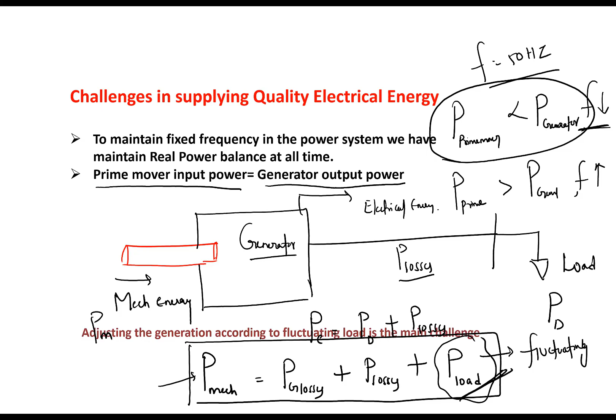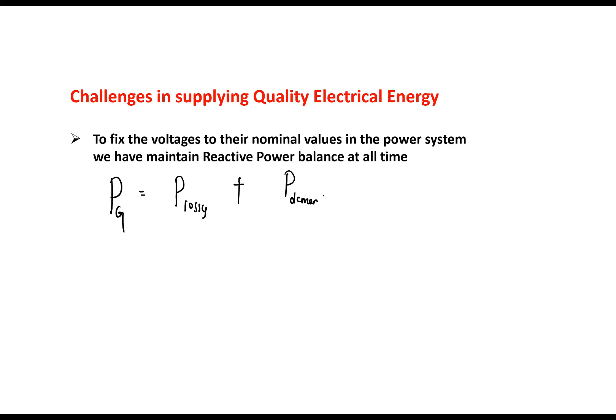Adjusting the generation according to the fluctuating load is one of the main challenges that we face in our power system. Now, how to fix the voltage? We have learned what affects the frequency. What will affect the voltage? The voltage is affected by the reactive power. In the previous case, total power generation should match with the total losses plus total demand, all added together. This is the real power balance equation. The total generation must match with the total losses plus total demand. If this equilibrium is maintained, then your frequency will be equal to nominal frequency, which is 50 Hertz.